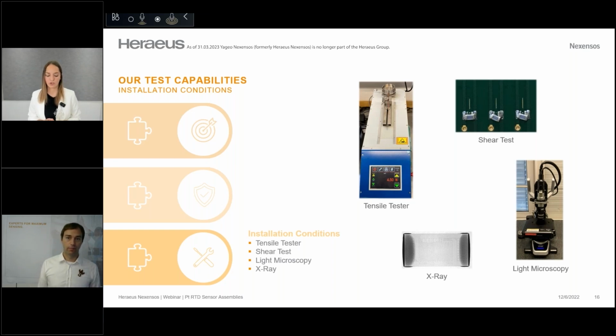Yes, this is our last slide concerning the test capabilities in-house. All the sensors need to be installed, and therefore we have some test equipment to ensure a good installation condition of our sensor assemblies. So, for example, with the tensile tester, we can measure the strength, and Dominic also referred to it. We can measure the strength between the lead wires and the cable. For example, for the EC3032, we specify a tensile strength of approximately 100 Newton. If we now install an SMD part on a PCB into that assembly, we could have a shear test to evaluate the soft soldering connection of the SMD part to the PCB board.